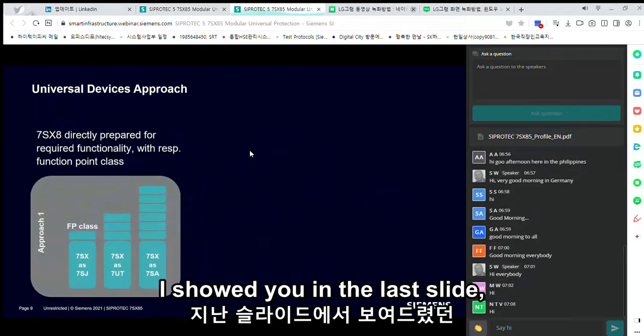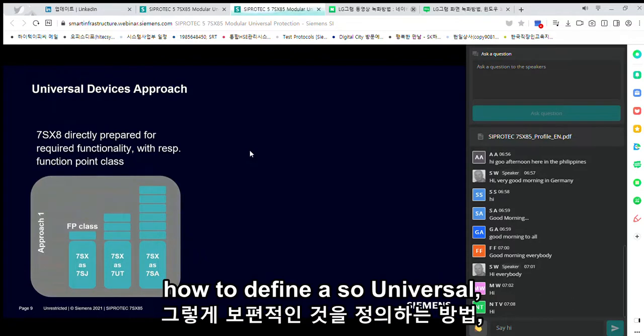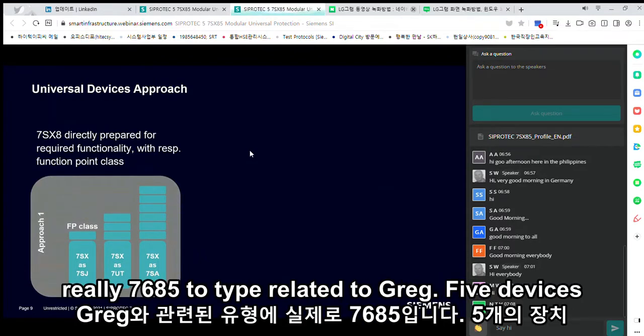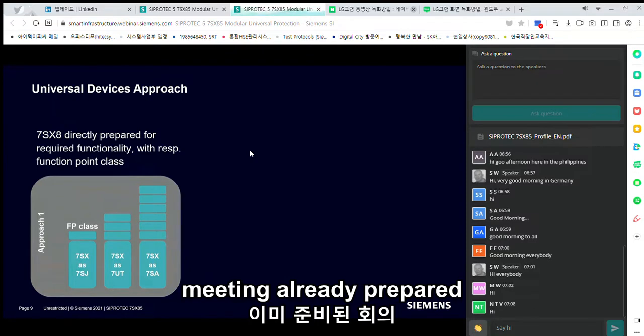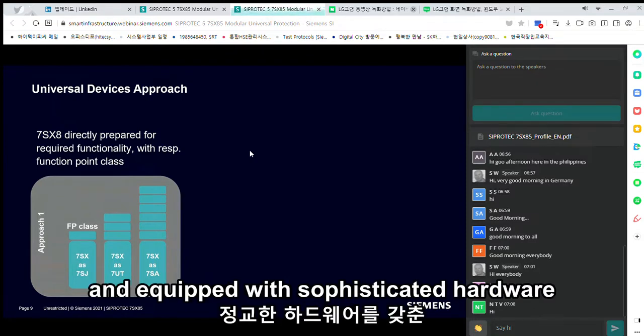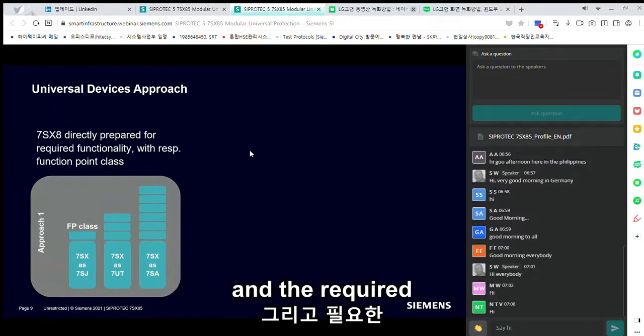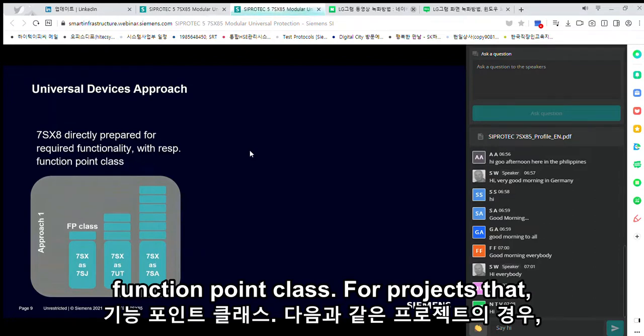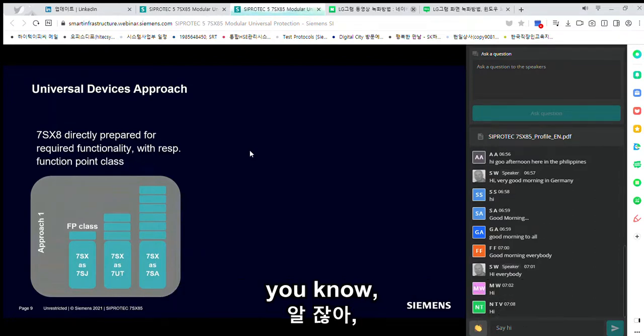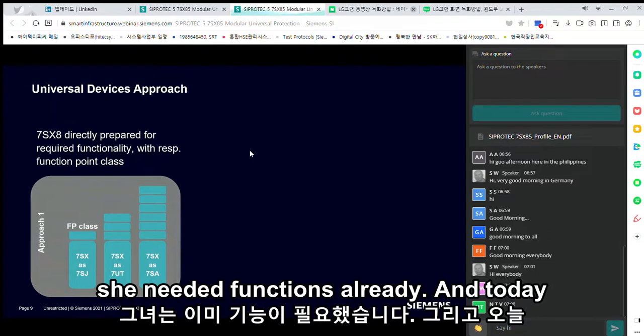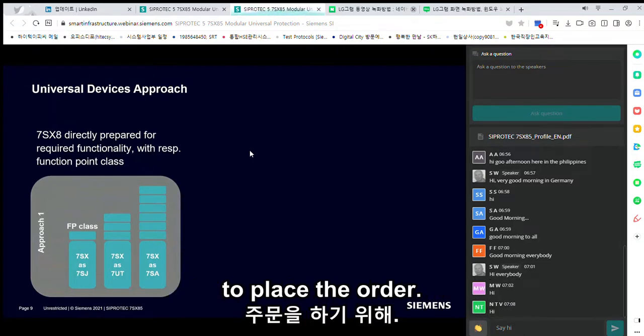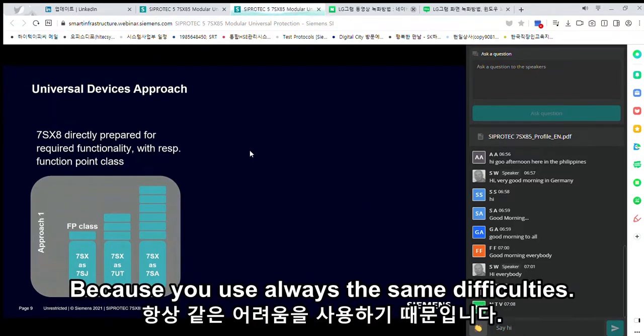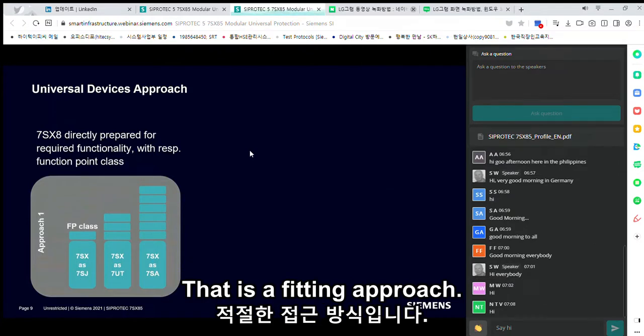I showed you in the last slide how to define the universal relay 7SX85, equivalent to the type-related SIPROTEC 5 devices, meaning already prepared and equipped with the fitted hardware and the required function point class. For projects where you know the needed functions already at the date you place the order, maybe because you always use the same typicals, that is a fitting approach.